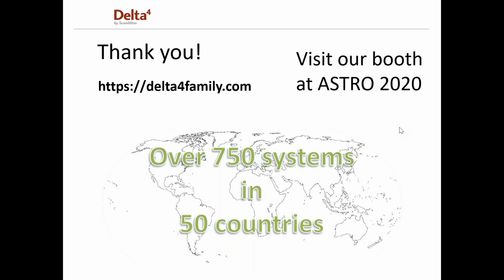Lastly, it says, can the board trolley be used on a standard Linac? Yes, it can. Board trolley is another word for the trolley we developed for the MR Linac. That's the trolley we sell with tomotherapy and also sell with Halcyon. So if you're going to use that on a standard Linac, all you have to do is match the height of the couch and then slide the Phantom over onto the couch. So if you have a Tomo unit, you order the board trolley, and then you can use it on your conventional Linac as well.